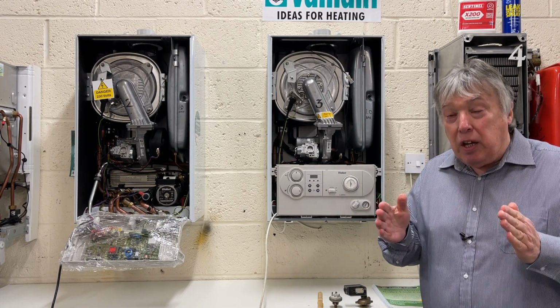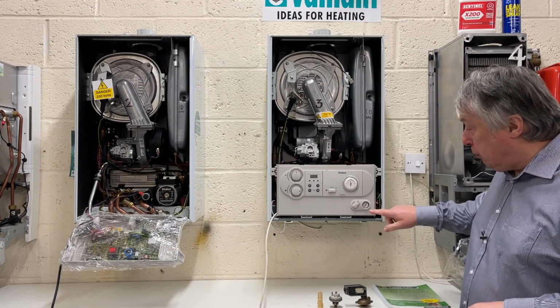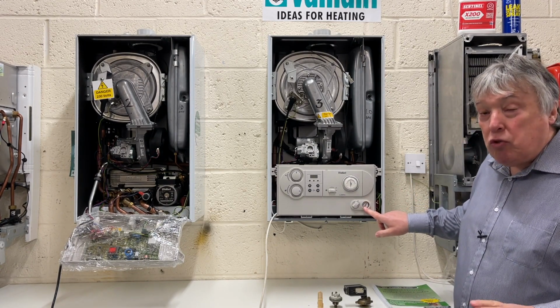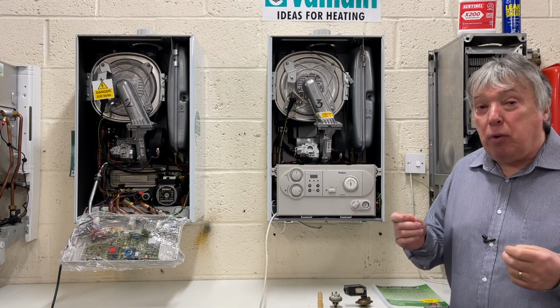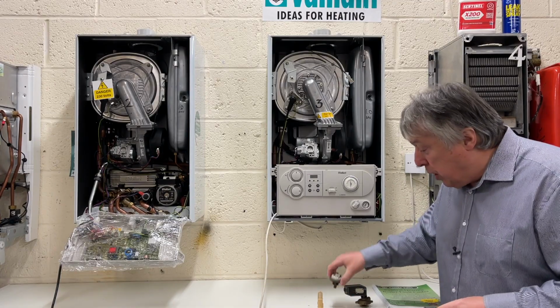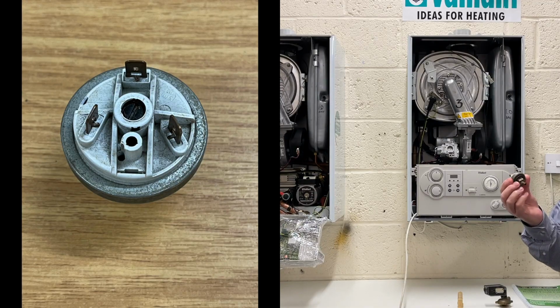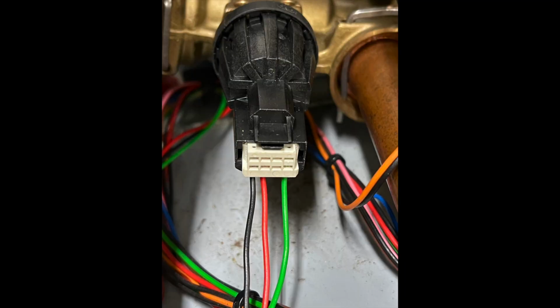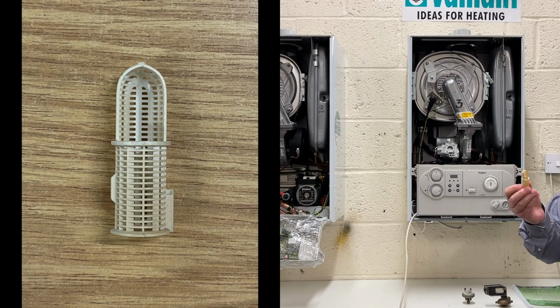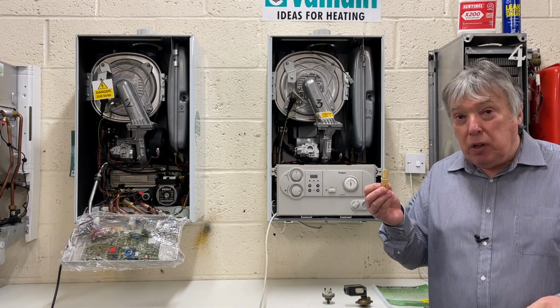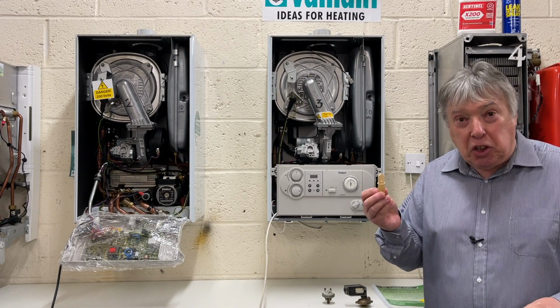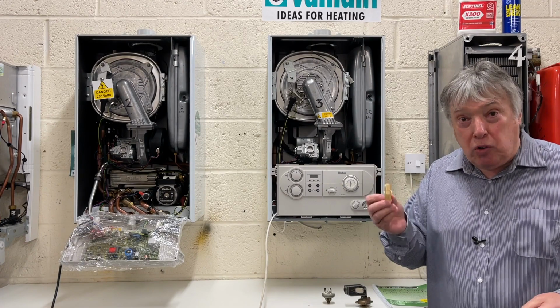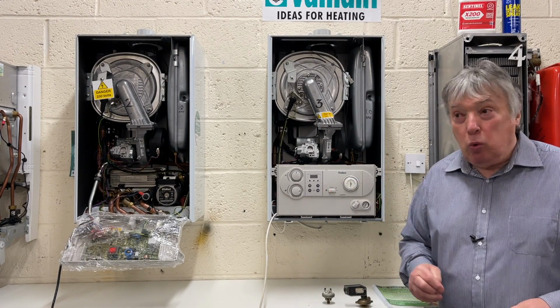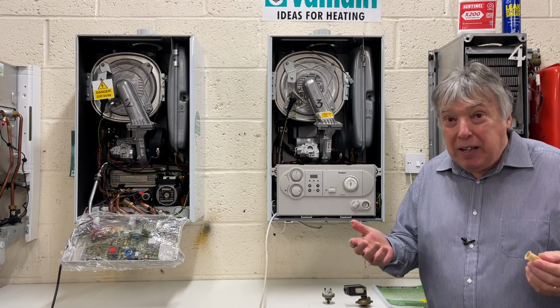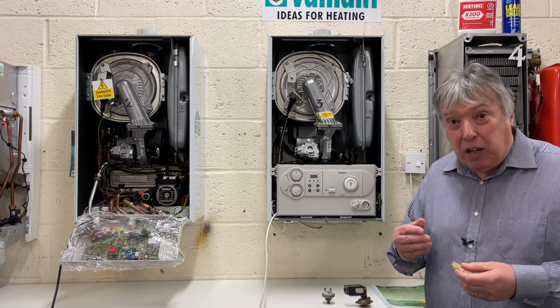Vaillant is saying it's a water pressure fault. So look at the gauge, maybe that's all that's wrong. But there may be other underlying problems as well. For example, there will be a water pressure switch in some boilers. Vaillant have got a sensor. Vaillant will have also a canoe, which is what we call these plastic canoes, and they get blocked up. They're only for the protection of the secondary heat exchanger, the plate-to-plate one. But if it gets blocked, you'll get an error code here, F22, you've got no water, which obviously isn't. It's just that the sensor can't see it.